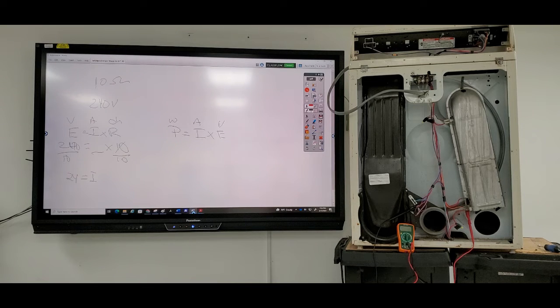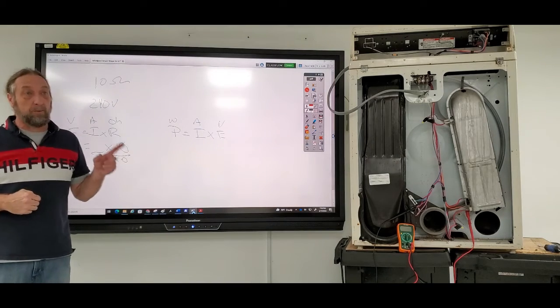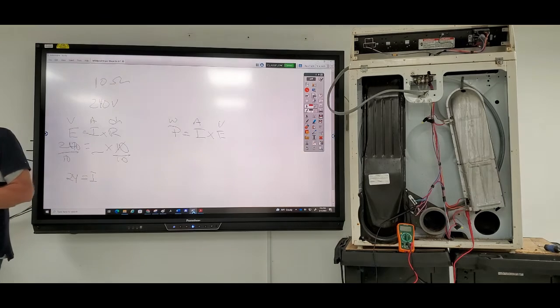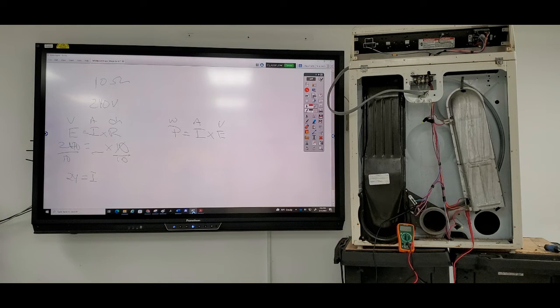That's about a good 70% of the max amperage when that dryer is fully running with everything on. It's just like a stove. A stove's on a 50 amp circuit, but if you turn on every burner on top, every element in the oven, the clock running and the light on, you're probably pulling about 40 to 41 amps, but you're on a 50 amp breaker.